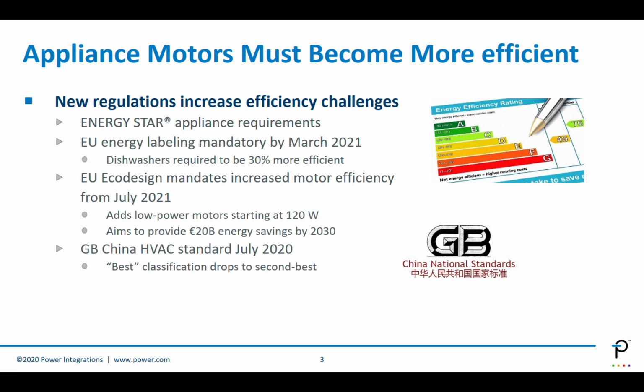And they also added single phase motor efficiency, which needs to meet IE2 levels starting 2022. There is also a new EU energy labeling, which is mandatory starting 2021. It will simplify labeling and consumer decision making, but will also raise the efficiency level. For example, in the case of dishwashers, they will be required to be 30% more efficient. Similar targets also in China with the new GB regulation, which sets new efficiency standards for HVAC, came into effect July this year, and the previous best-in-class efficiency is now second best.